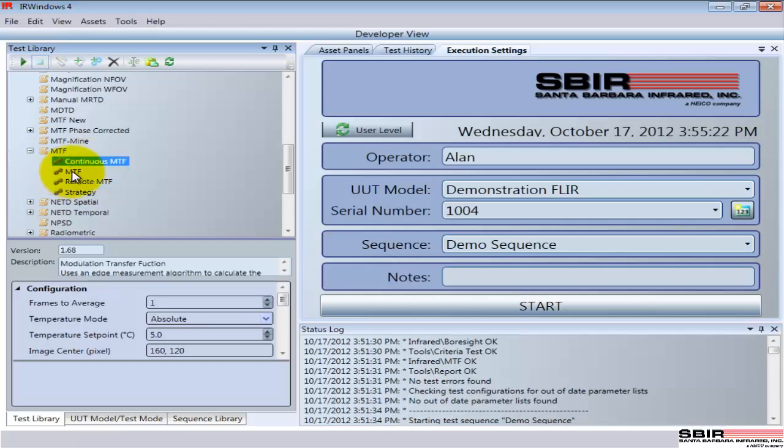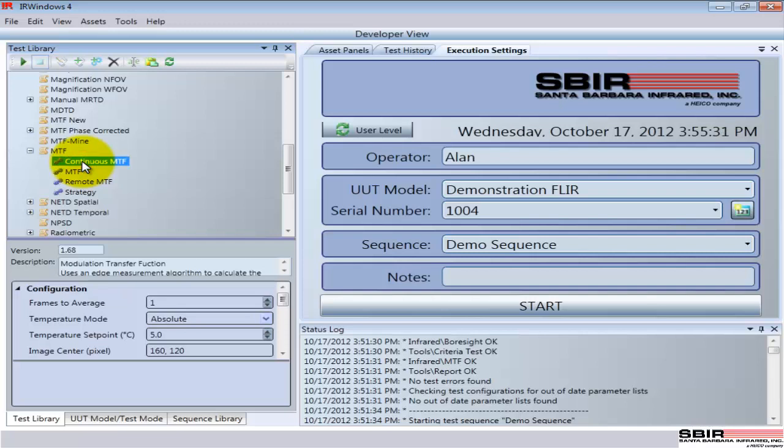That way I can run different configurations depending on what I want to try to accomplish. The configuration can be based on the device that's being tested, or if I have different goals. For instance, I can have this MTF that averages four images. This one is a single image, so I can quickly run one test or the other and see what the results look like. These tests can be individually run.